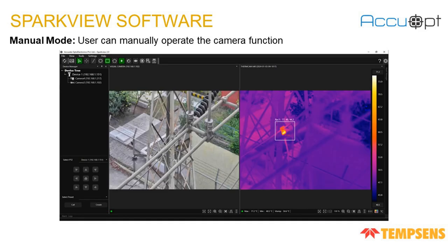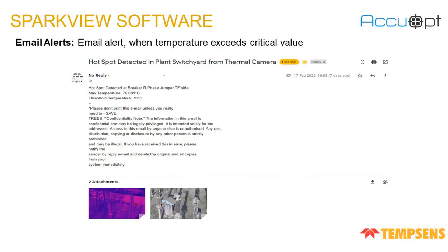This is the software in manual mode. The user can manually operate the camera functions like pan and tilt. This is a sample of our email alerts. When temperature exceeds the critical value, the automatic email will be forwarded to the concerned person with the maximum and threshold temperature and the area at which the hotspot has occurred.